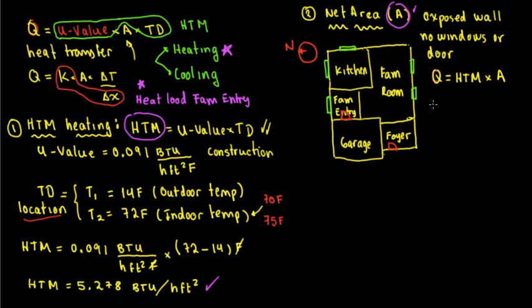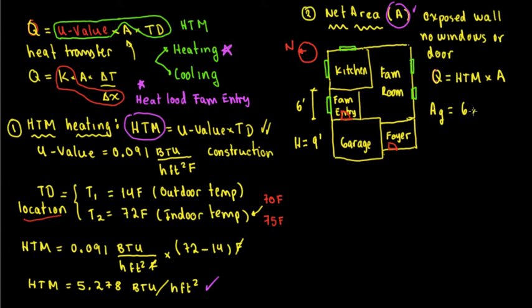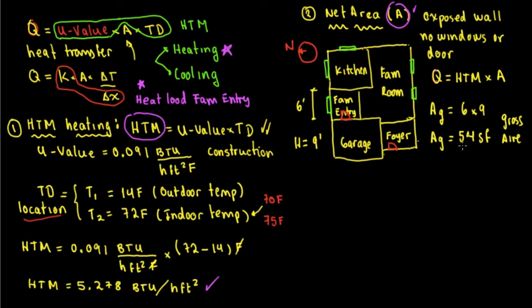The exposed area starts with the gross area. The exposed wall of the family entry is going to be 6 feet, and the ceiling height H is 9 feet. So the gross area is going to be 6 times 9, which equals 54 square feet. That is the gross area.